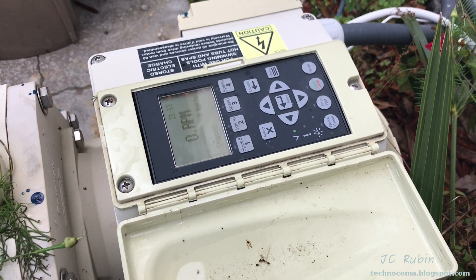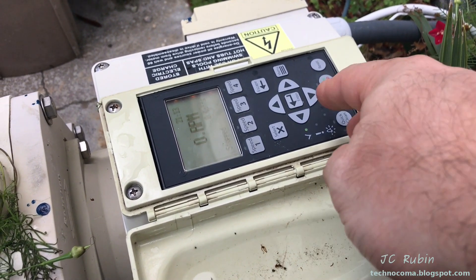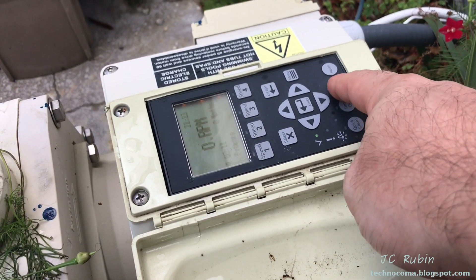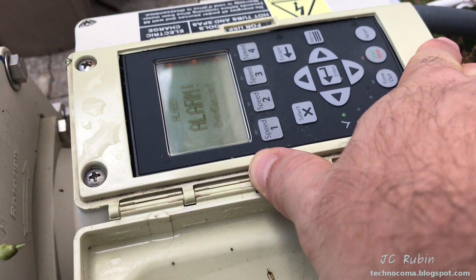This time of year we got the pool running in the evening and it's starting to go foul. I had a look and noticed that when the pump is running, or when you attempt to start the pump, we hear a little knock and get this overcurrent alarm. That can't be good at all.